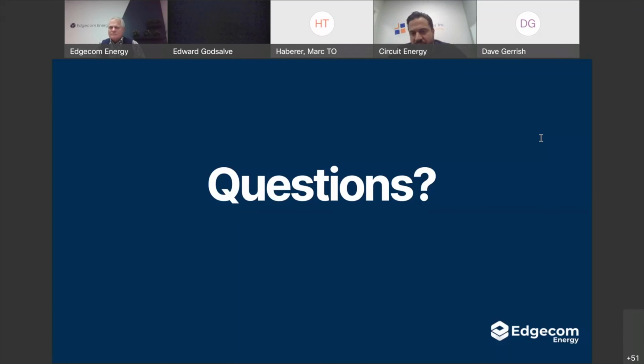Jonathan's asking, do we need a connection impact assessment application to our LDC? That's part of the services we offer, included in our packages for both the PCS system and the UPS. The UPS is a much easier process because it's not a bi-directional asset, whereas the PCS is. So we would need to submit a connection impact assessment to the local distribution company, typically involving our protection philosophy, the type of switches, and their ability to isolate the batteries if need be at any point without the intervention of our network operations center.